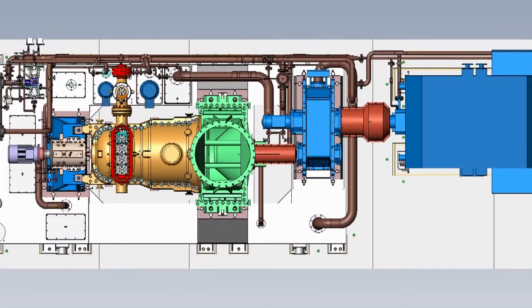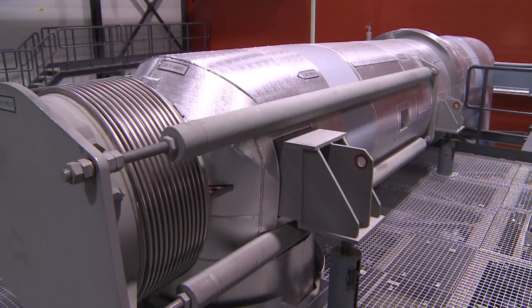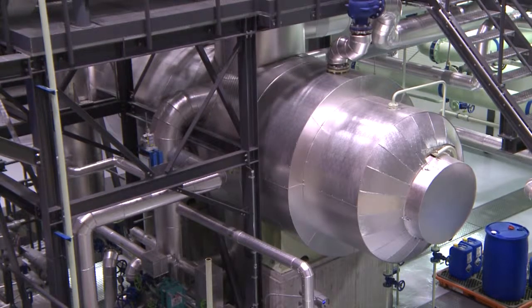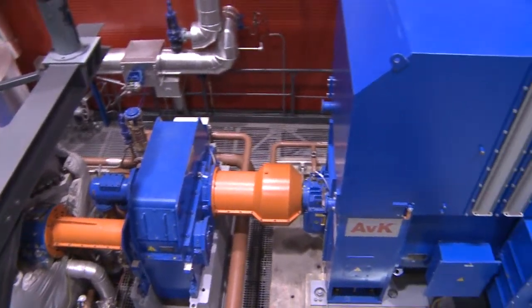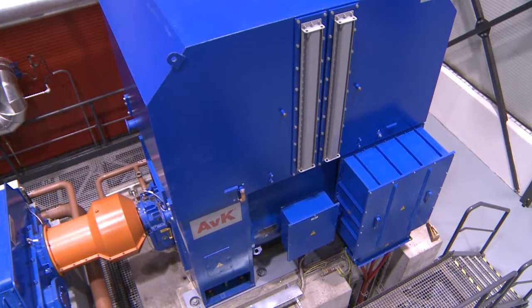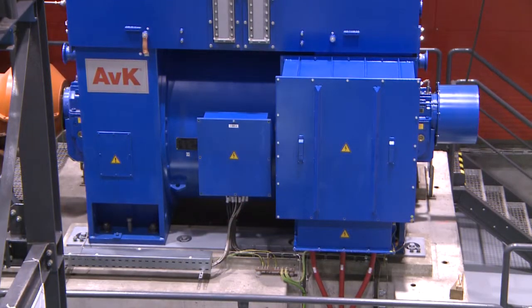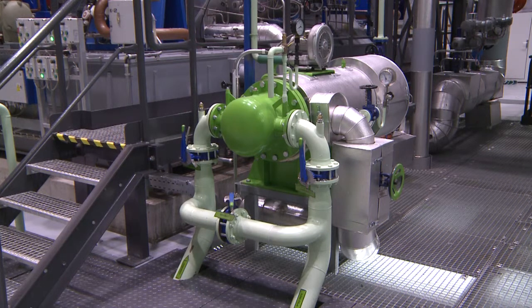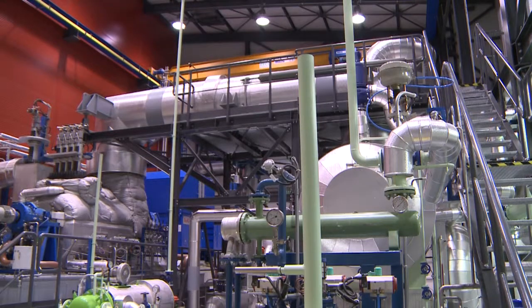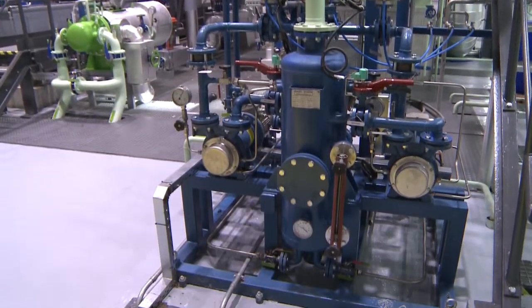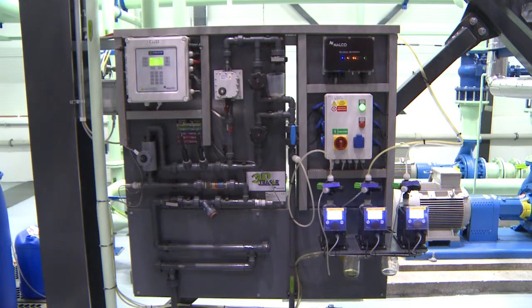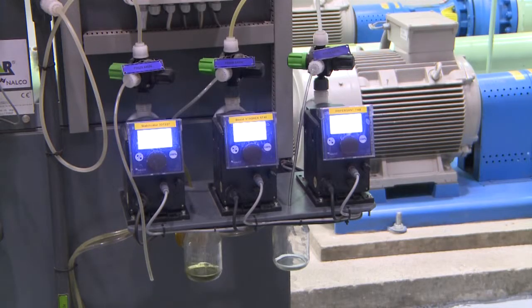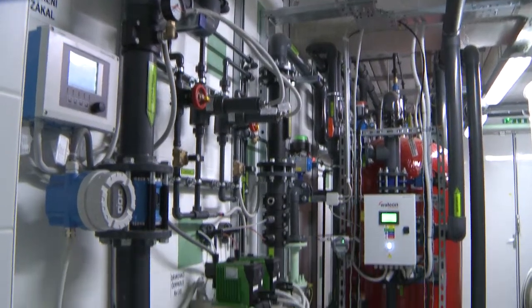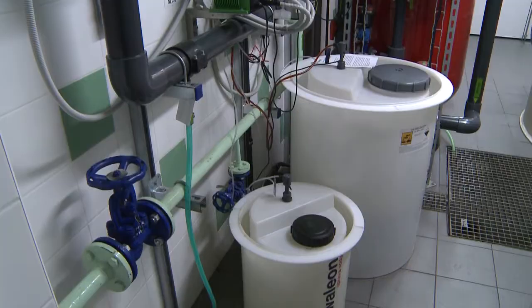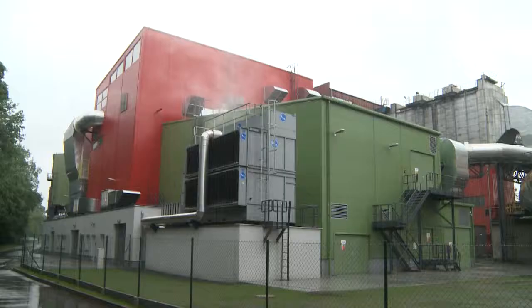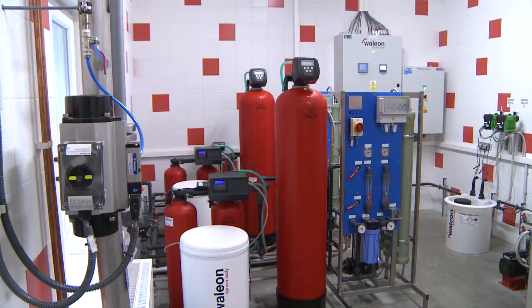The steam goes upright out of the turbine to the horizontal piping and then downwards to the heat exchanger. The power from the turbine through the gearbox and generator is delivered to the electric grid. The seal steam condenser forms part of the turbine set, as well as the vacuum station. Cooling water is treated with chemicals against corrosion of the piping in the set of equipment. Equipment for filtering the cooling water is located in a separate part of the water treatment plant. The cooling towers are installed outside of the turbine hall.